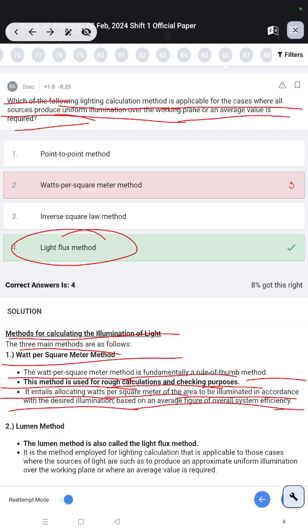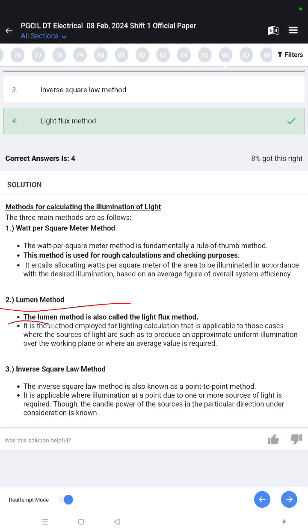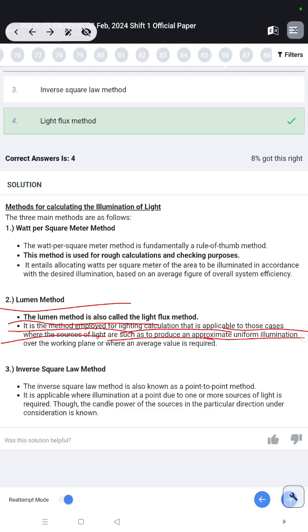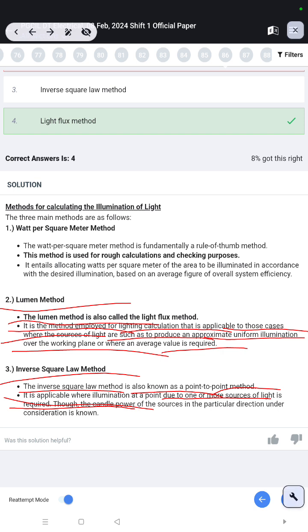Lumen method. The lumen method is also called the light flux method. It is the method employed for lighting calculation that is applicable to those cases where the sources of light are such as to produce an approximately uniform illumination over the working plane or where an average value is required. Inverse square law method. The inverse square law method is also known as the point-to-point method. It is applicable where illumination at a point due to one or more sources of light is required and the candle power of the sources in the particular direction under consideration is known.